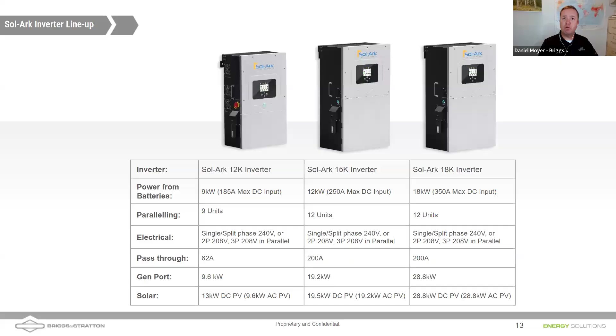We can take 200 amps in on grid, 200 amps right back out on load. If grid goes down, the grid input will disconnect us from grid. We have a third port, a gen port, which stands for general, not generator. And that can be used for a generator, smart load, or AC coupled solar. And we're going to talk today about how to program a Sol-Ark for each of those scenarios.